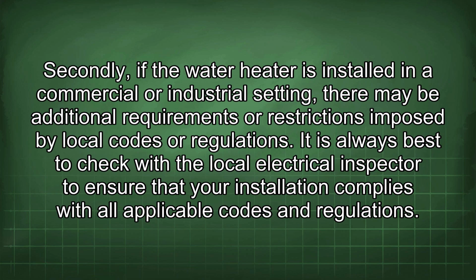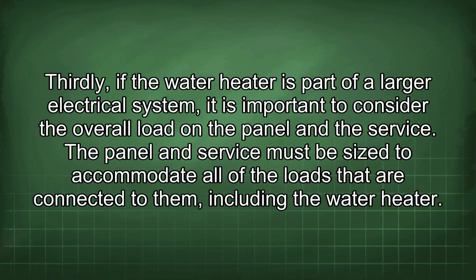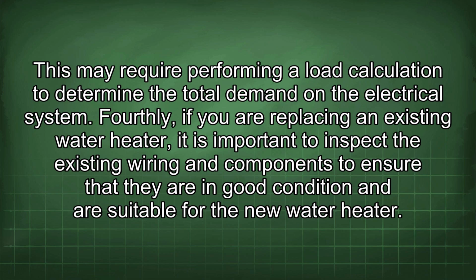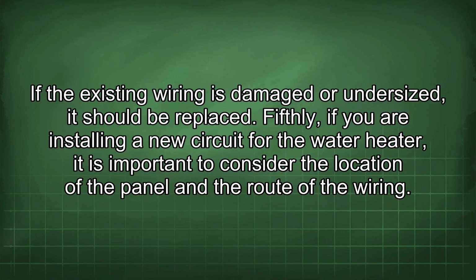Thirdly, if the water heater is part of a larger electrical system, it is important to consider the overall load on the panel and the service. The panel and service must be sized to accommodate all of the loads that are connected to them, including the water heater. This may require performing a load calculation to determine the total demand on the electrical system. Fourthly, if you are replacing an existing water heater, it is important to inspect the existing wiring and components to ensure that they are in good condition and are suitable for the new water heater. If the existing wiring is damaged or undersized, it should be replaced.